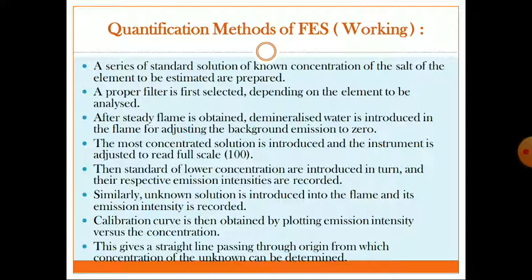And a proper filter is first selected depending on the element to be analyzed. That means suppose we have prepared sodium chloride solution, then we have to use a sodium filter in the flame photometer. And when we prepare KCl, potassium chloride, in that case we have to insert a potassium filter into the flame photometer. Likewise, we have to insert the proper filter.